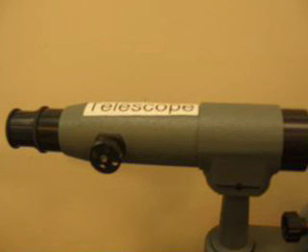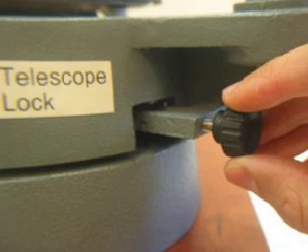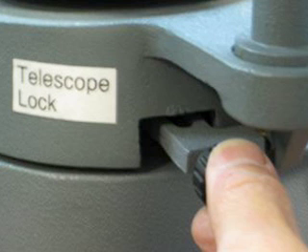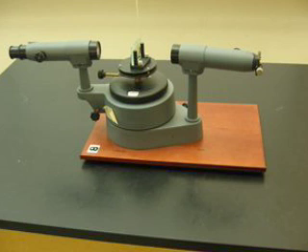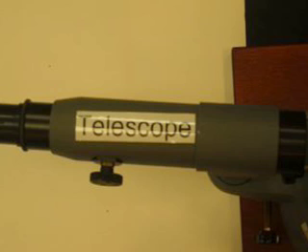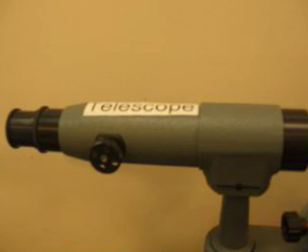The first step in using your spectrometer is to position the telescope. Locate the telescope lock at the base of the telescope and turn it gently. The telescope should now be free to move. Position it opposite the collimator with the grating table in between. Now you are ready to focus the telescope. This is a two-step process.